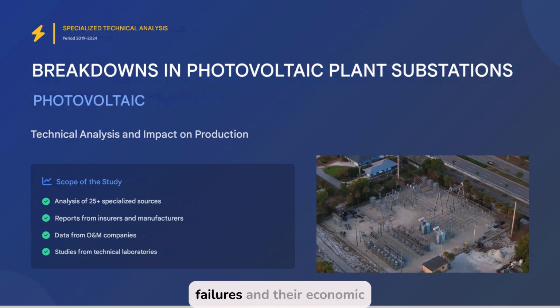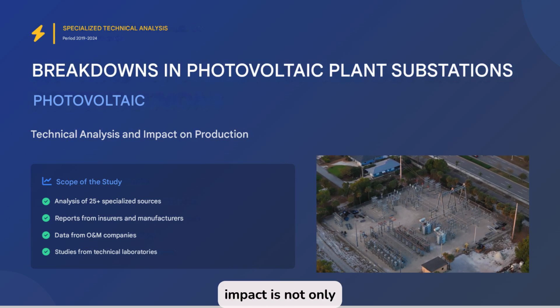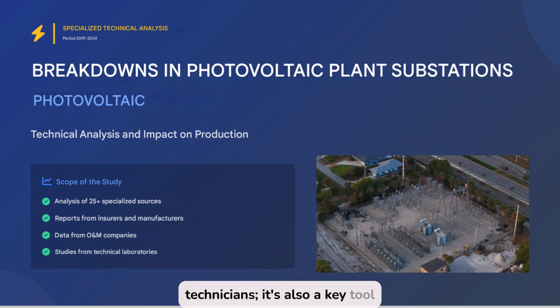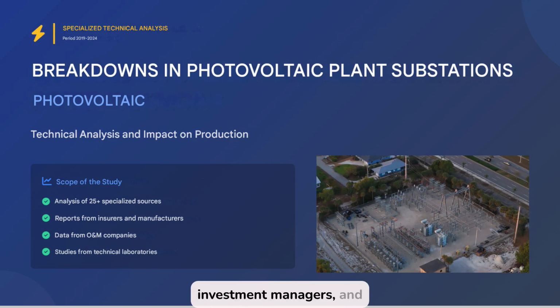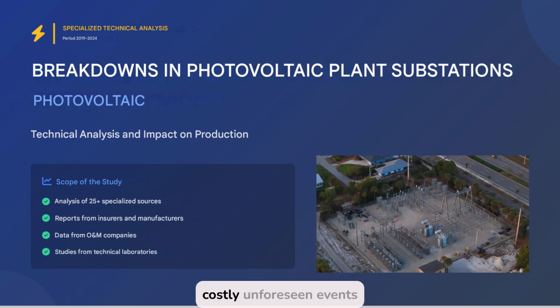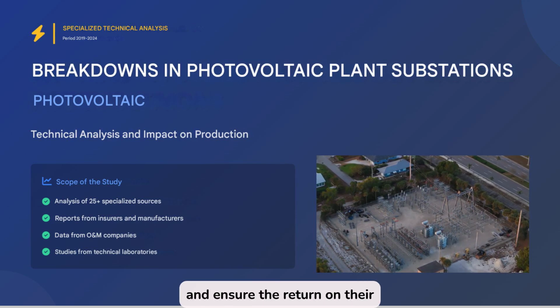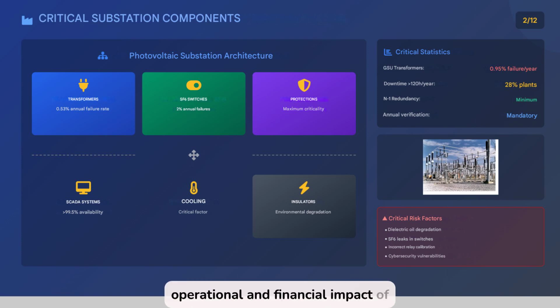Understanding the root causes of failures and their economic impact is not only useful for technicians, it's also a key tool for financial directors, investment managers, and insurers who want to avoid costly, unforeseen events and ensure the return on their renewable energy projects. To understand the operational and financial impact of breakdowns in a photovoltaic plant, we must start with the substation. It's not just about understanding the installed equipment, but also identifying which ones are critical, their probability of failure, and the consequences they can generate. It is in this infrastructure where any interruption can result in considerable losses.